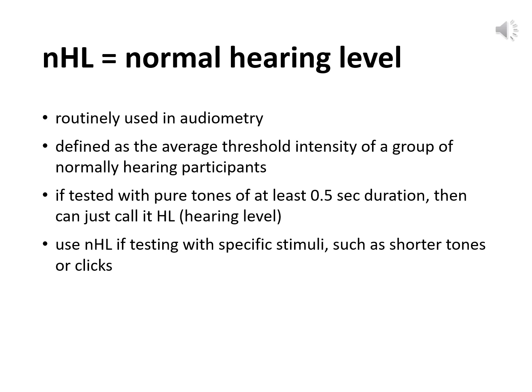Therefore, this scale is location-specific and needs to be recalculated if the evoked potential system is moved to another environment, because in the other environment, the background noise levels would change.